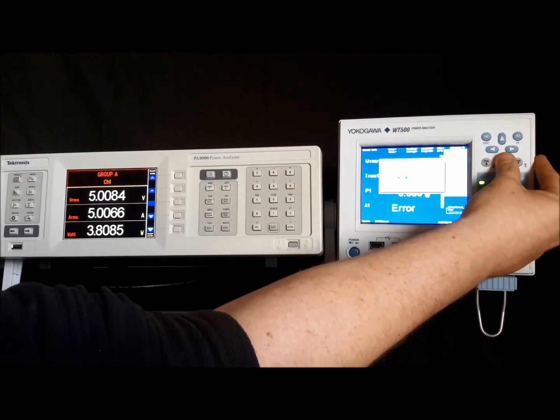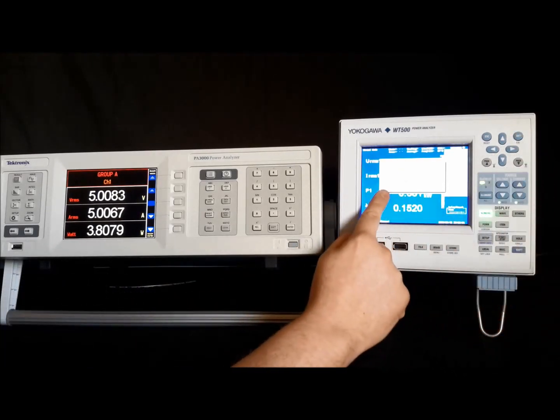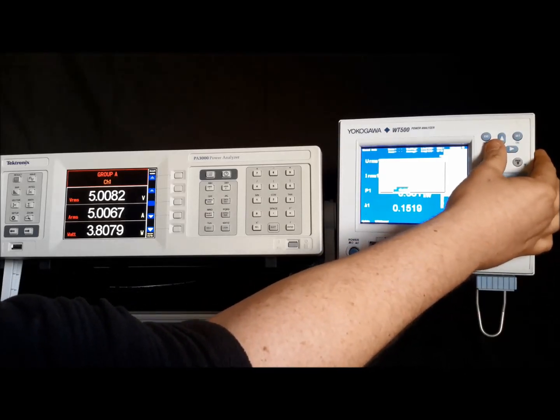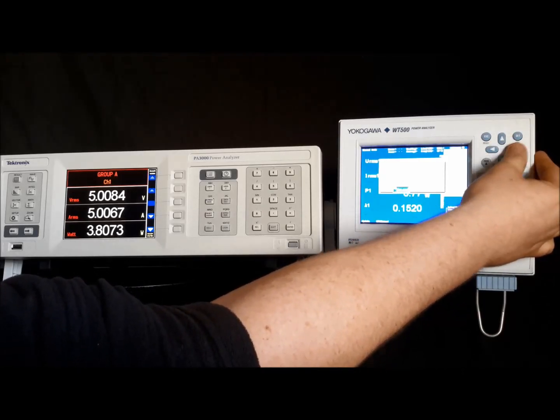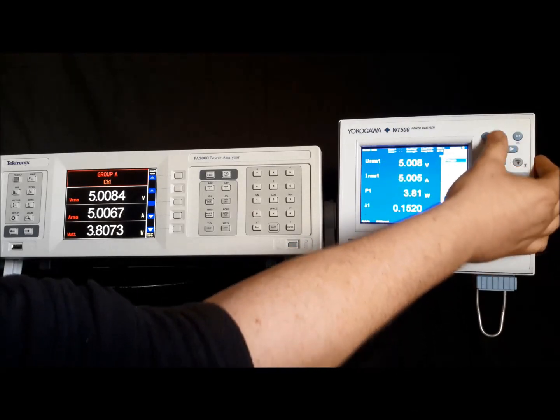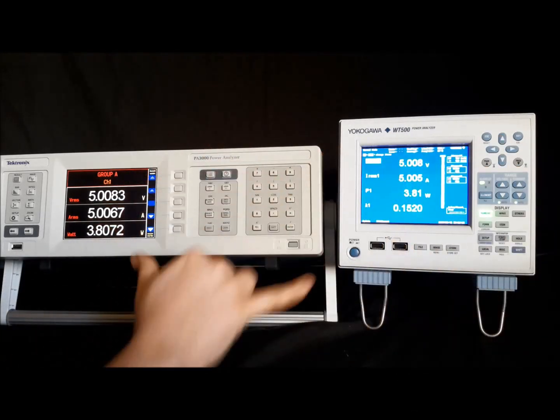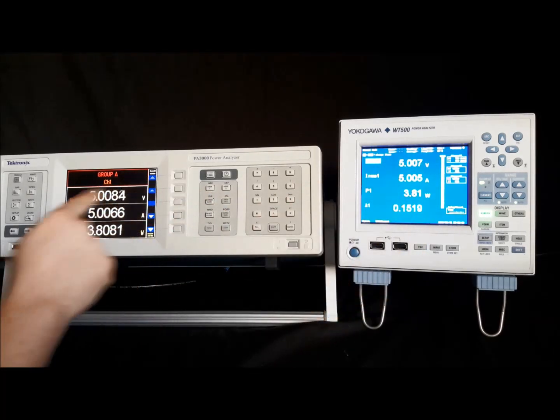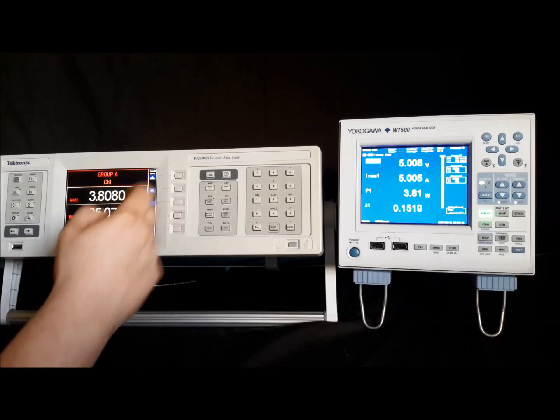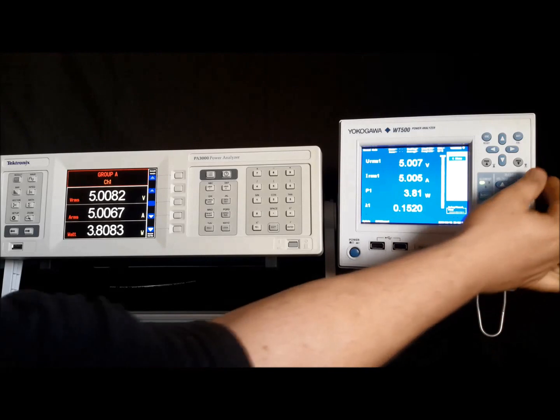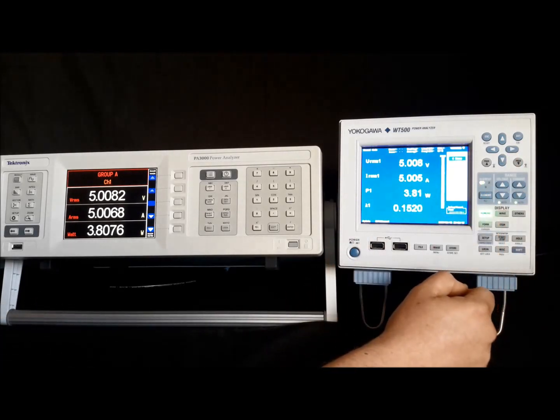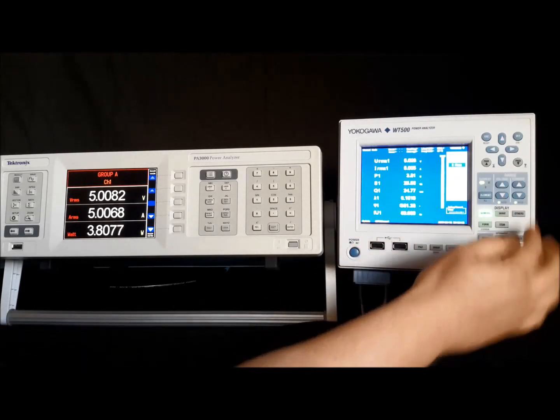I'll go to setup, ranges, external sensor. Now here the sensor ratio, it says millivolts to amps, so it wouldn't be 1 millivolt, it would be set as such. So what you see is 5 volts, 5 amps. Same on both units. Same power reading with the power factor displayed there. On the Tektronix unit you can move down and look at more parameters as well. With the Yokogawa unit you can go to form and choose a variety of different formats of displaying more and more data if you want to.